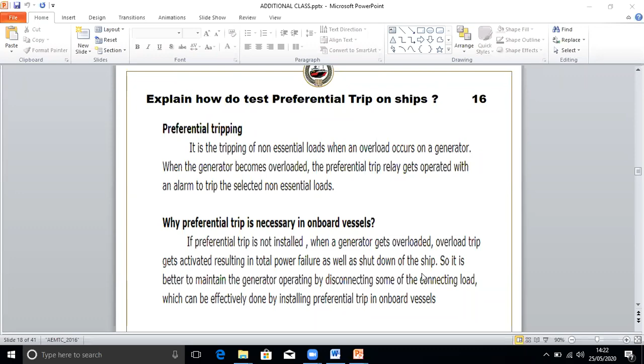It goes like this: 5 seconds, air conditioner, ventilation; 10 seconds, refrigeration, cargo plant; 15 seconds, deck equipment. Now after 20 seconds, if the overload still exists after tripping the non-essential services, then the overload trip gets activated. After 20 seconds, it trips the whole ship circuit. So the preferential trip is actually tested by a current injection method.